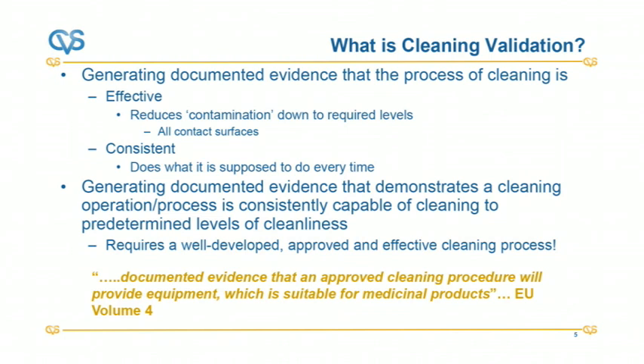Okay, so that's a little bit about cleaning. Now, what is cleaning validation? Whenever we talk about validation, usually it means generating documents: test protocols, test reports. You quite often see comical photographs of validation, people with paperwork about this high. The more paper you've got, the more files you've got, the better the validation. That is in jest, but don't judge the quality of the validation by the weight of the paperwork. It doesn't always follow. Or the more signatures you have, the better. That doesn't follow either. So we're generating documented evidence as part of the validation that the cleaning is effective, so it reduces contamination down to the required levels.